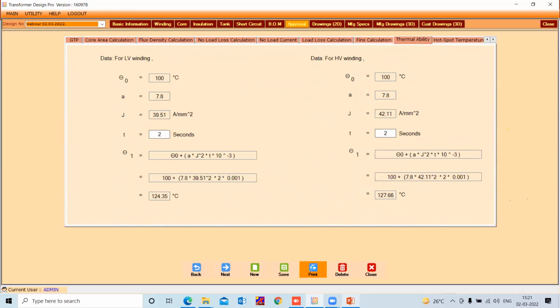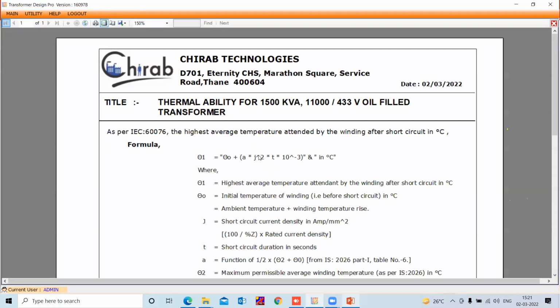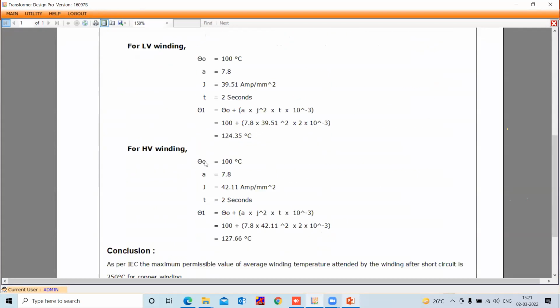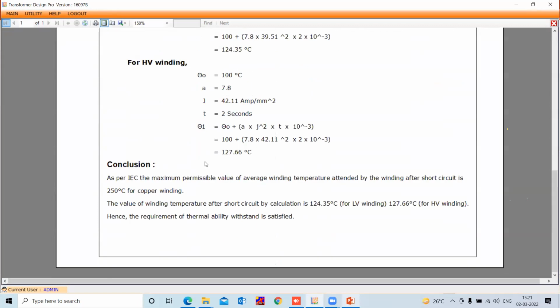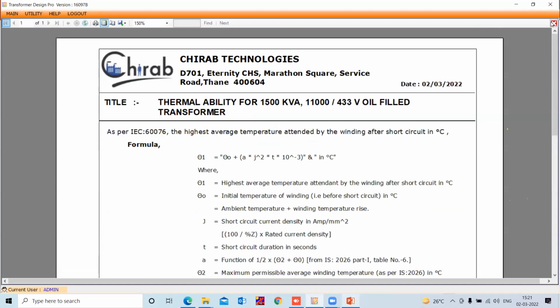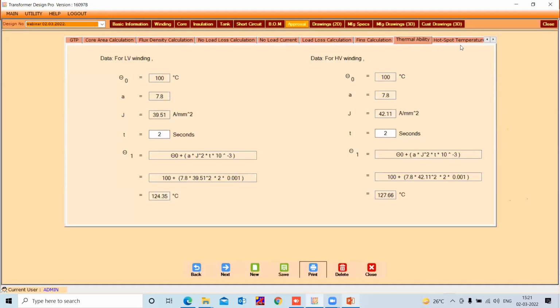In the printout, you will get the report like this. You can see the formulas, abbreviations, calculations, and conclusion. As per IEC, the maximum permissible value of temperature attained after short circuit is 250 degrees Celsius for copper, and the calculated one is 124.35 for LV and 127.66 for HV. Hence, the requirement of thermal ability is satisfied. So this kind of report you will get to submit to your customers.